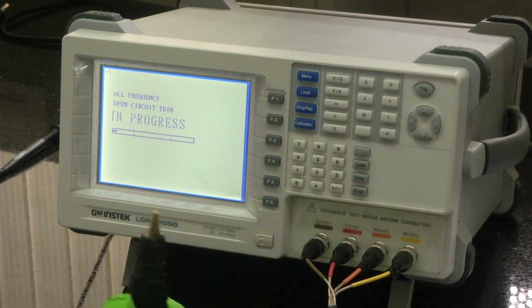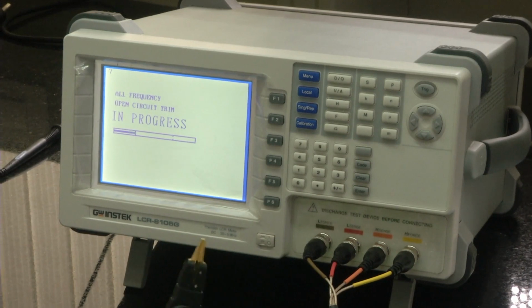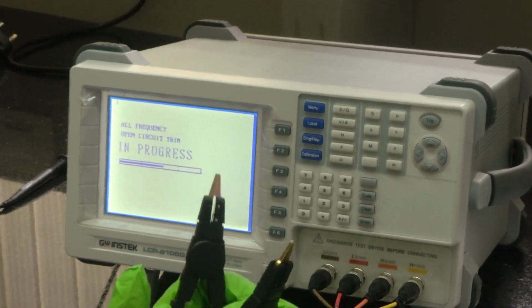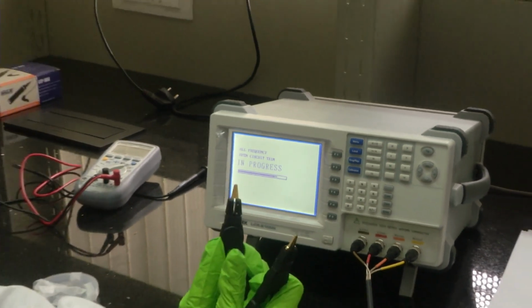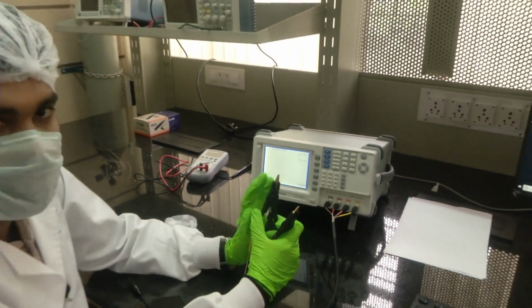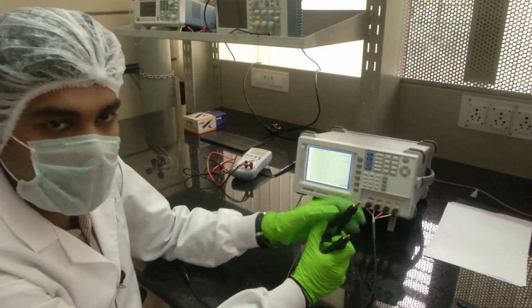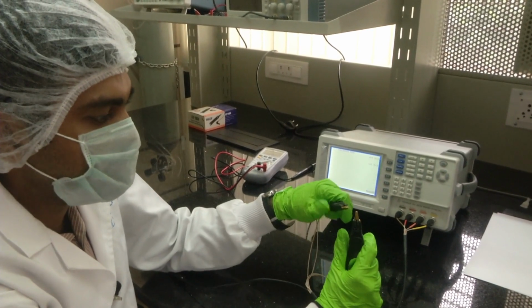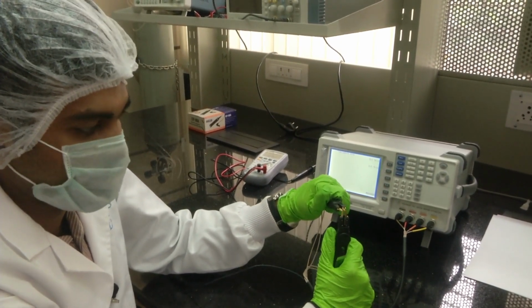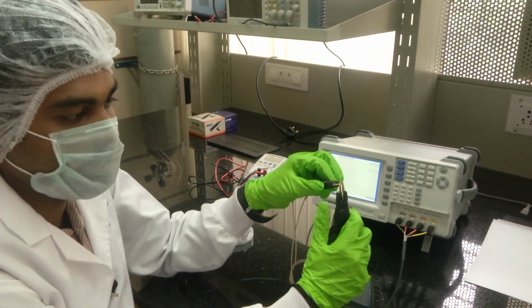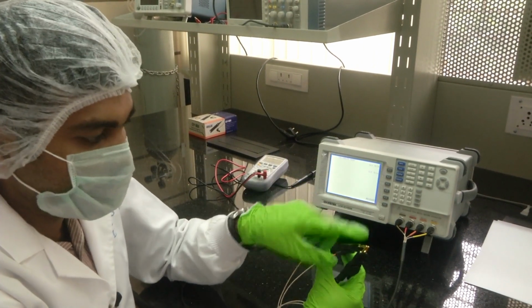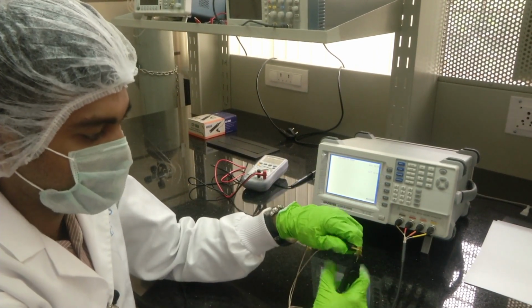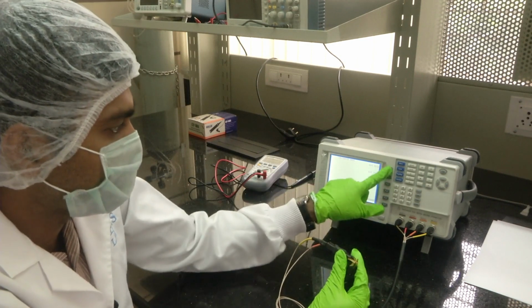Now, the calibration is in progress and I have kept it in open mode because this is an open circuit calibration. I have kept the probes in open mode and that calibration has succeeded. Now, let us repeat the calibration, but let us touch them together. So, they are actually shorted, correct? When you touch the probes together, they are shorted, but let us do the open circuit calibration with them shorted. Ideally, that calibration should fail. Let us see it happening.